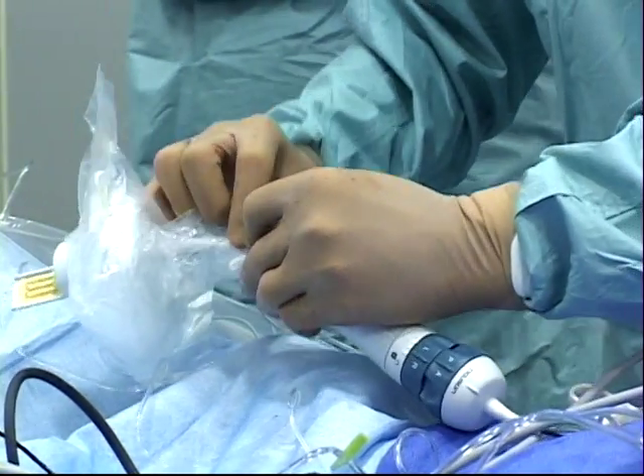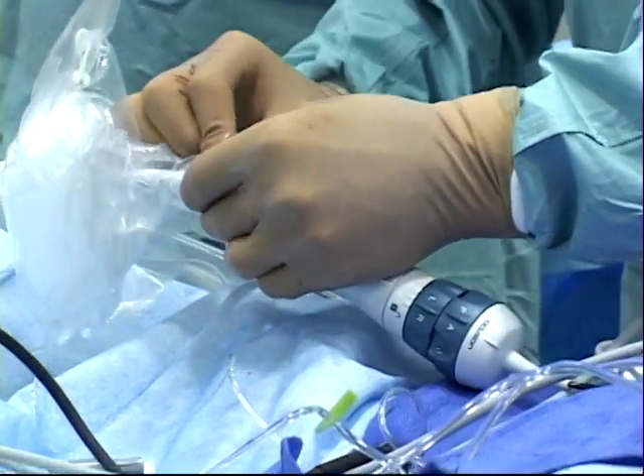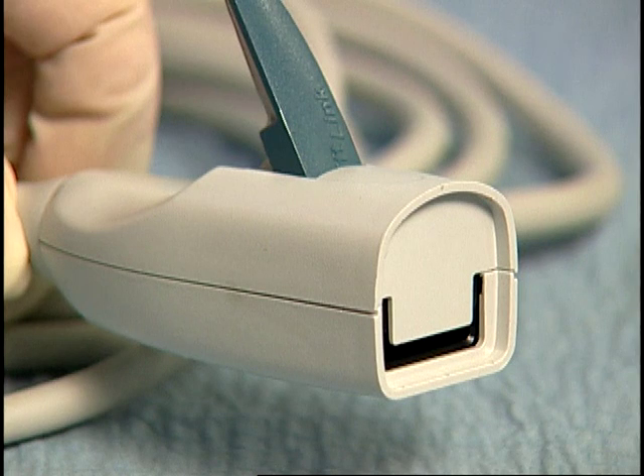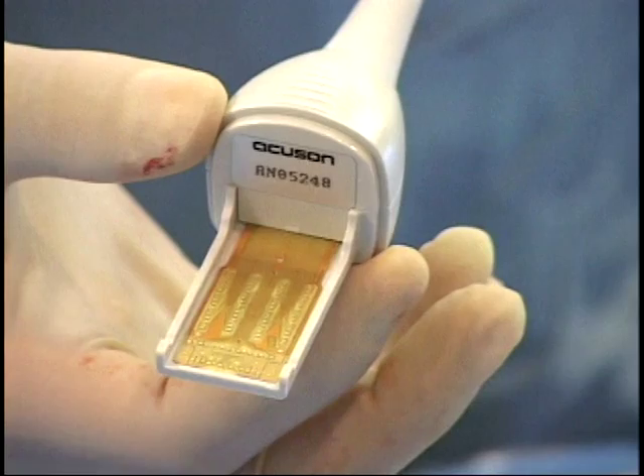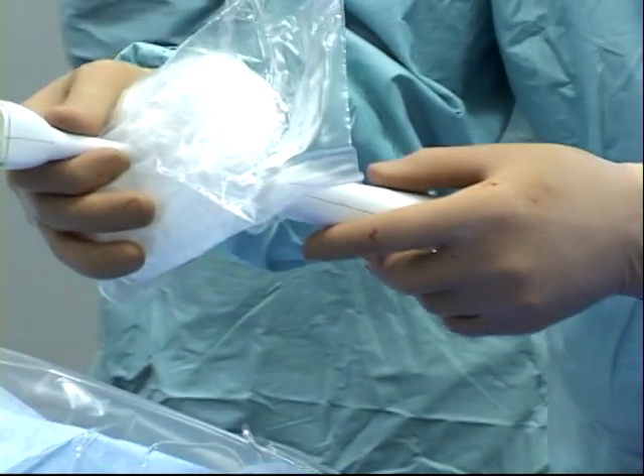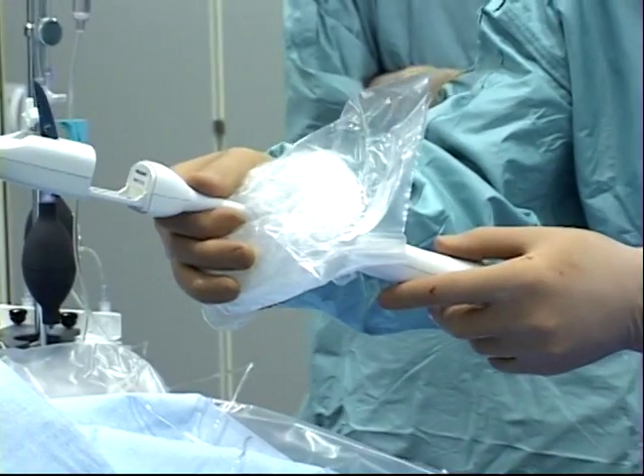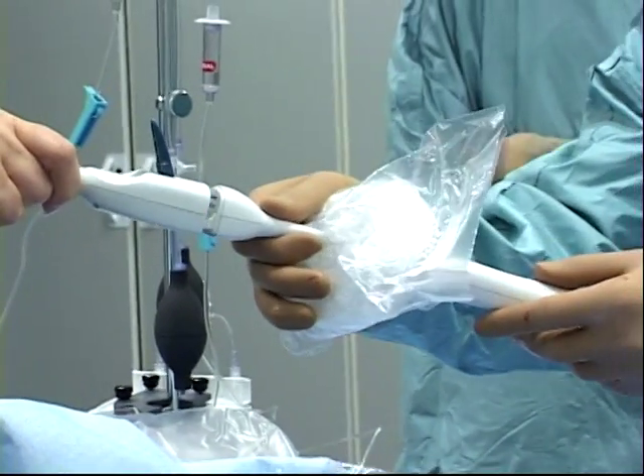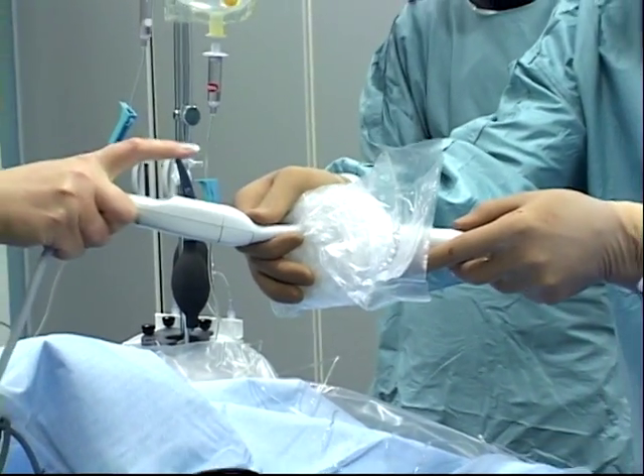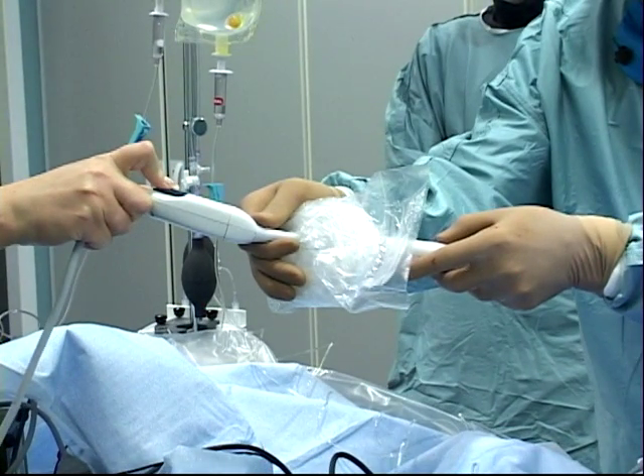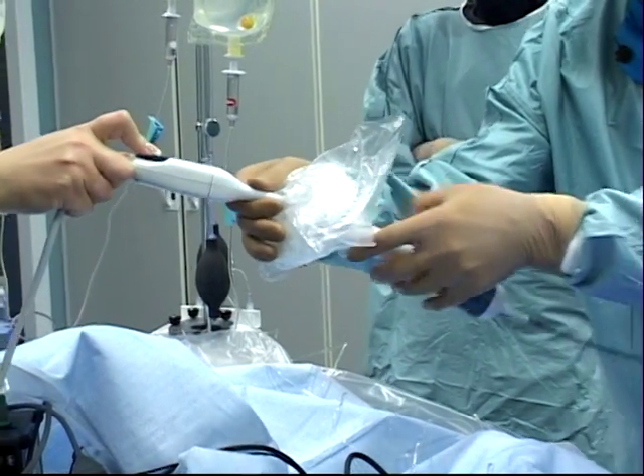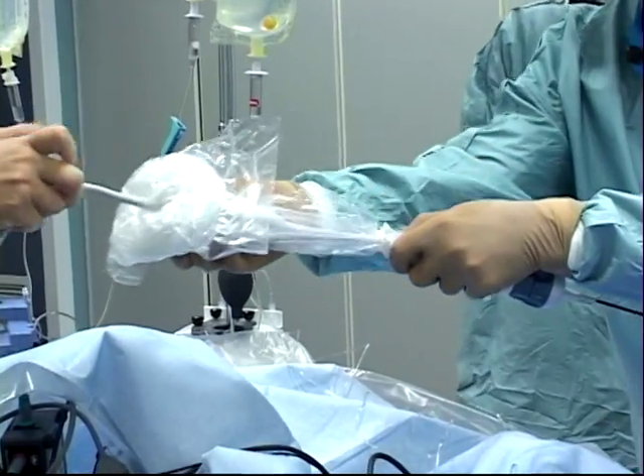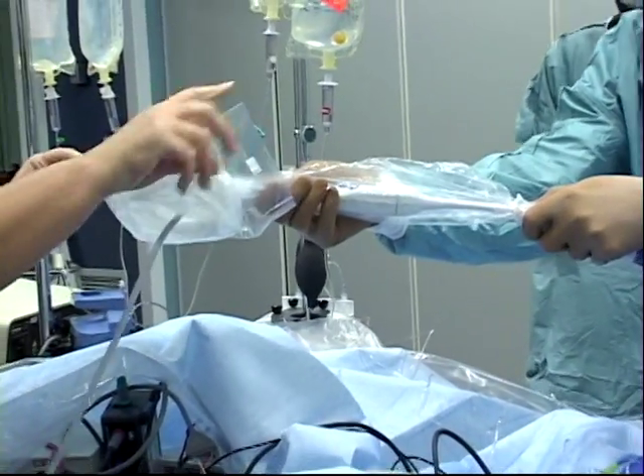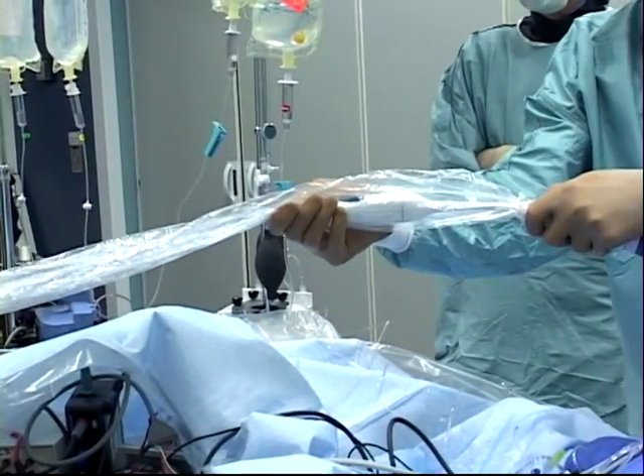The person outside of the sterile field holds the SwiftLink connector adjacent to the sterile field with a lever on the top end of the SwiftLink raised. The interconnect tab on the base of the catheter is inserted into the slot on the SwiftLink connector by the person within the sterile field. The person outside of the sterile field pushes the SwiftLink connector until it is flush with the edge of the ultrasound catheter and lowers the lever until it is locked and flush with the handle. Use the tabs on the sheath to roll it down over the SwiftLink connector cable.